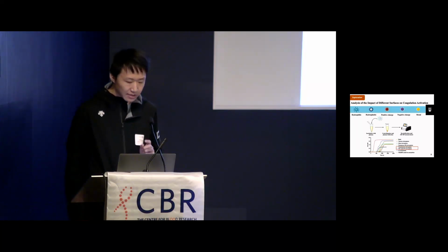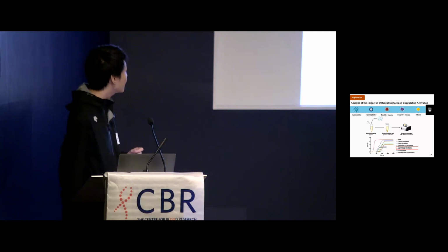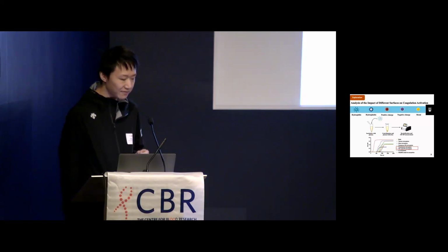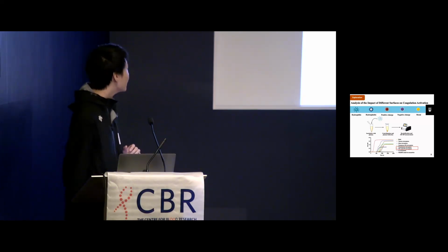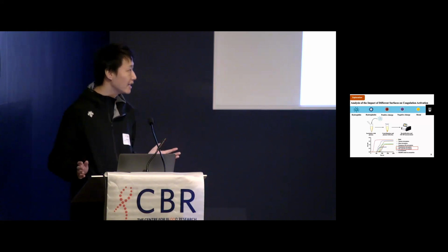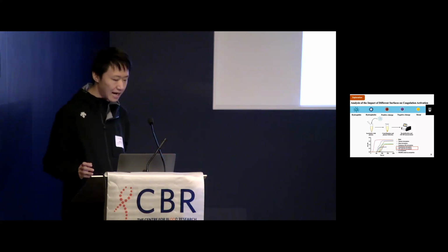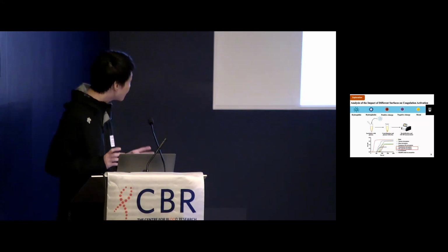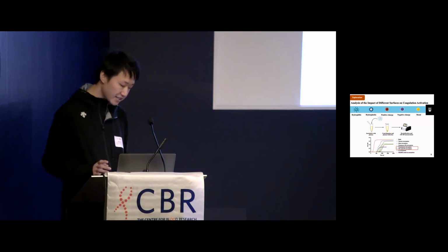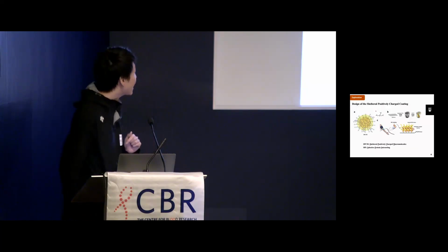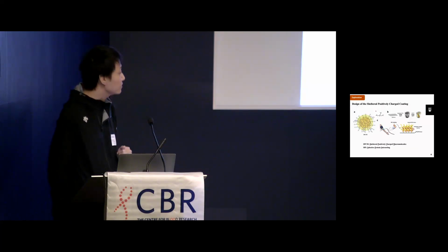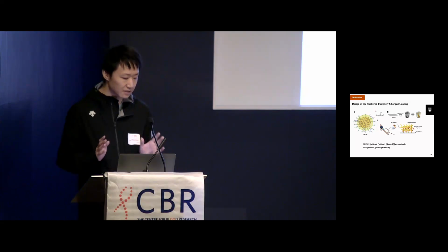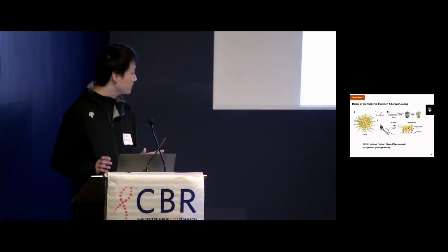First, we use a screening approach to identify whether there are any existing materials that can prevent surface-induced contact-activation. We tried different kinds of surfaces, including hydrophilic, hydrophobic, positive charge, negative charge, and metallic surfaces in their microparticle form. We incubated these surfaces with plasma, and to our surprise, we found that the plasma incubated with the positive charge surface did not show strong contact-activation. Even though we got these clues, we cannot directly use a positive charge surface because we all know this kind of surface usually does not work with our blood.